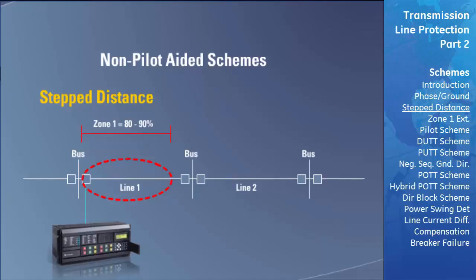The first zone of protection is set to underreach and extends from the beginning of the transmission line to 80 or 90 percent of the entire line's length. This zone has no intentional time delay, so if a fault occurs in this zone, the relay can be sure the fault is on its transmission line and can trip immediately. Zone 1 will not protect the last 10 to 20 percent of the line, known as the end zone. Faults in this area will not be seen by zone 1 and must be cleared by one of the other zones.